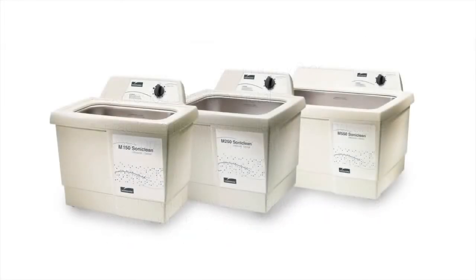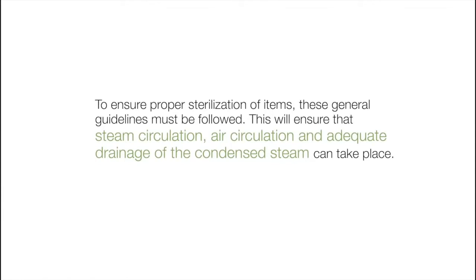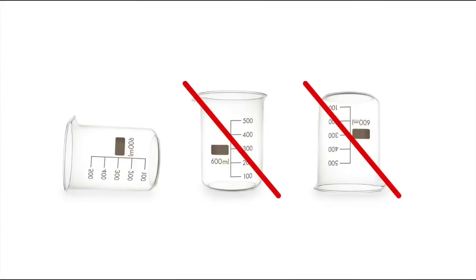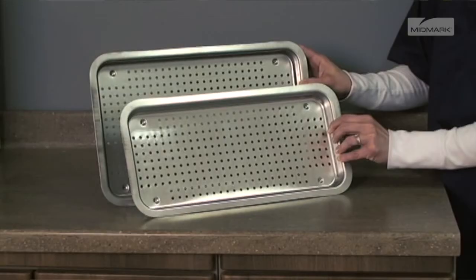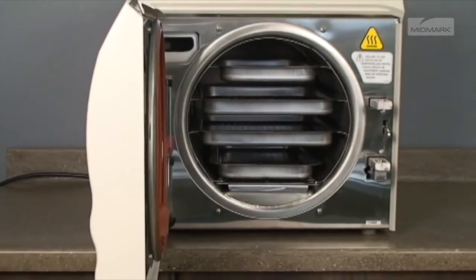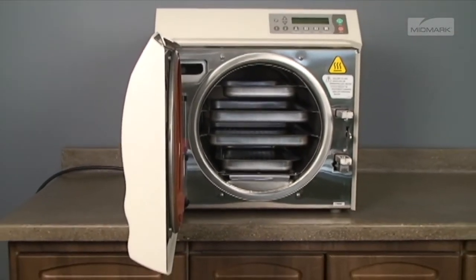Clean and dry instruments thoroughly before placing them into the autoclave. Improper cleaning may result in non-sterile instruments or damage to the unit. To ensure proper sterilization of items, these general guidelines must be followed. This will ensure that steam circulation, air circulation, and adequate drainage of the condensed steam can take place. All containers must be placed so the opening allows steam to enter and the air and condensate to drain from the container. Use only M9 or M11 trays in the appropriate sterilizer.